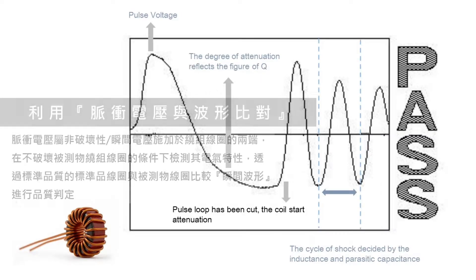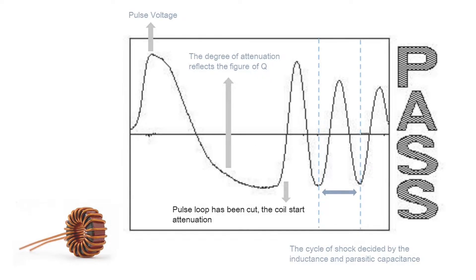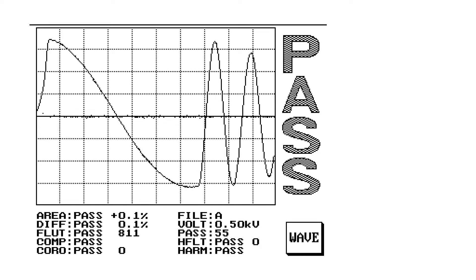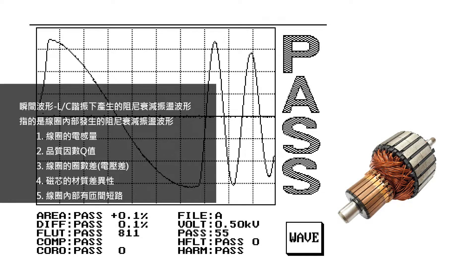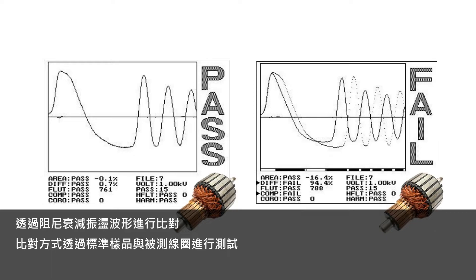Pulse Voltage and Waveform Comparison is the way Microtest 6920 detects layer shorts. The pulse voltage is a non-destructive, instant voltage applied on both sides of the winding to detect the DUT without damaging it. By comparing the waveform with the golden sample, we can judge the rotor quality.